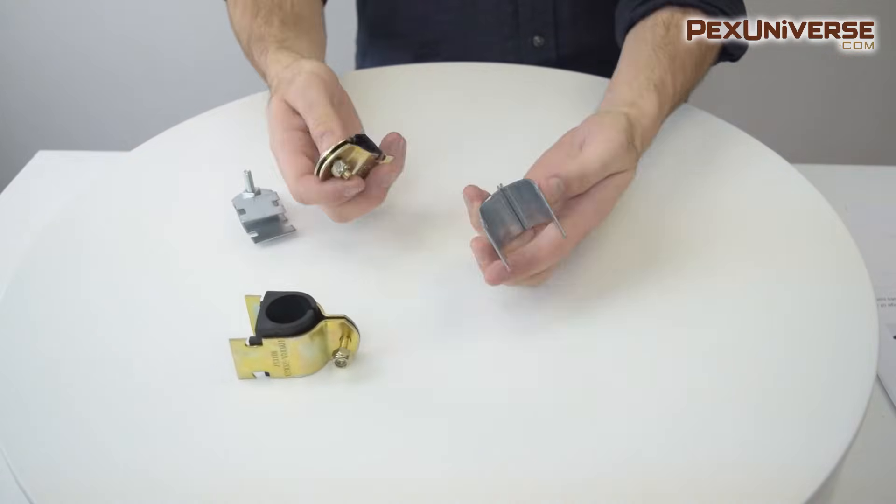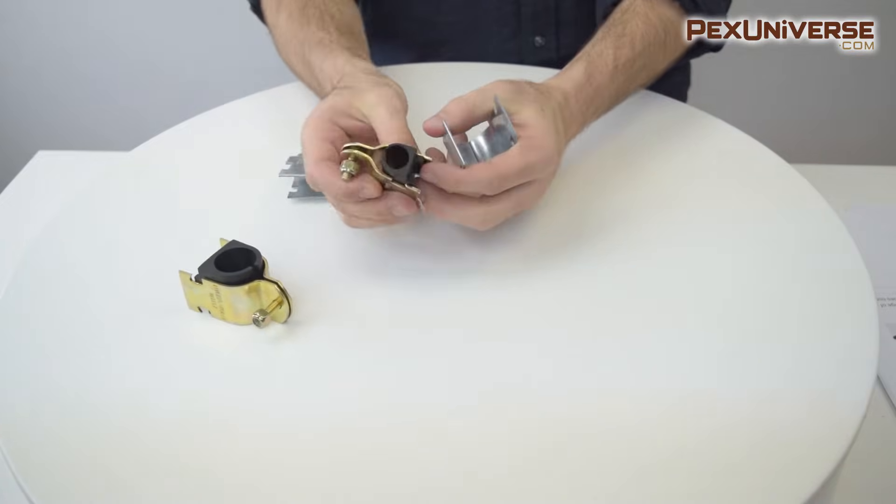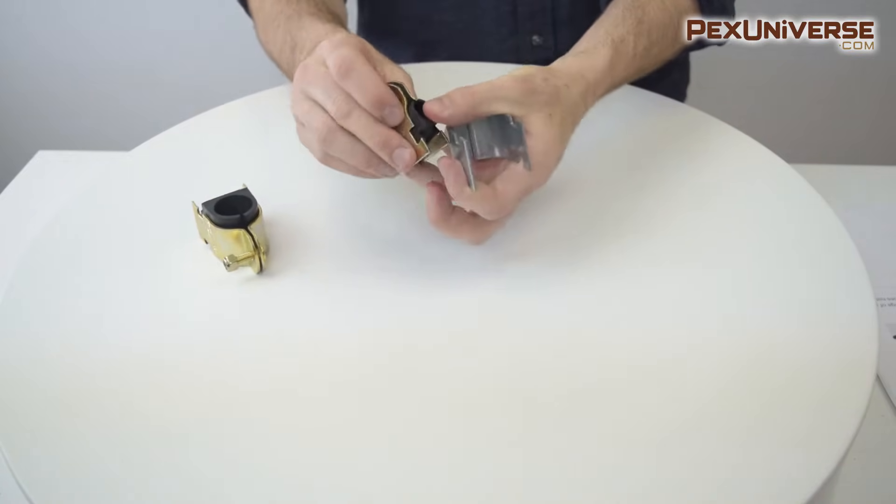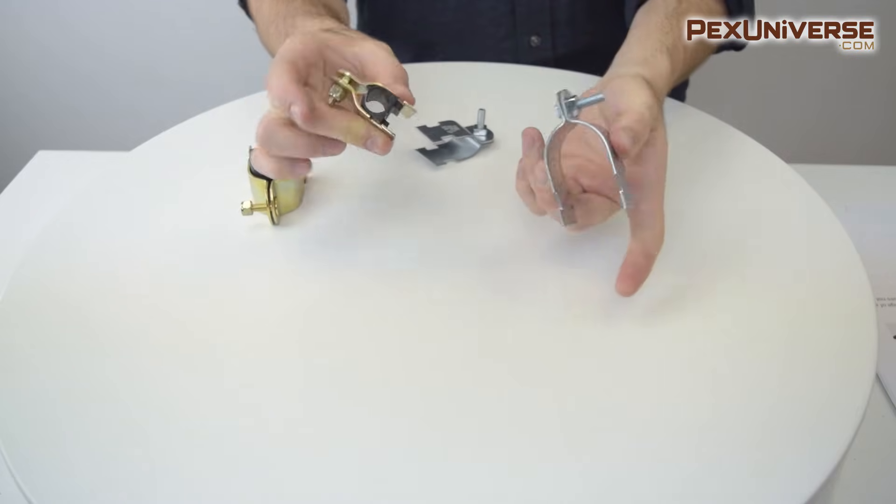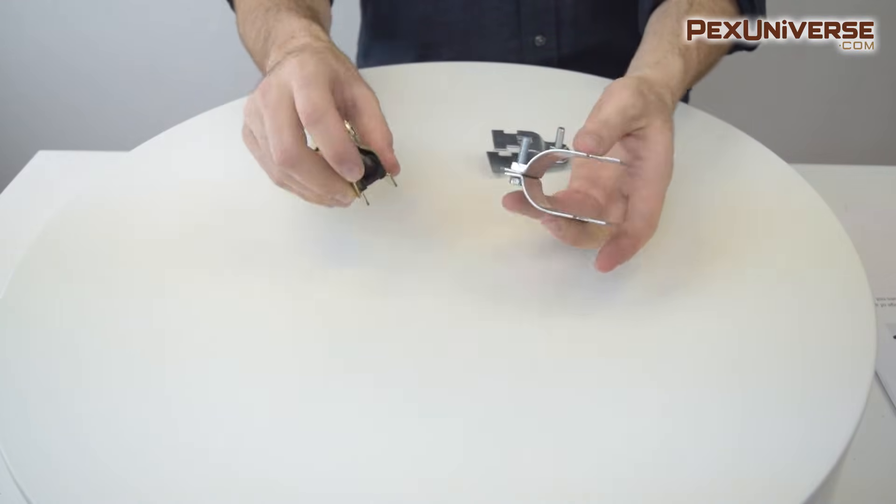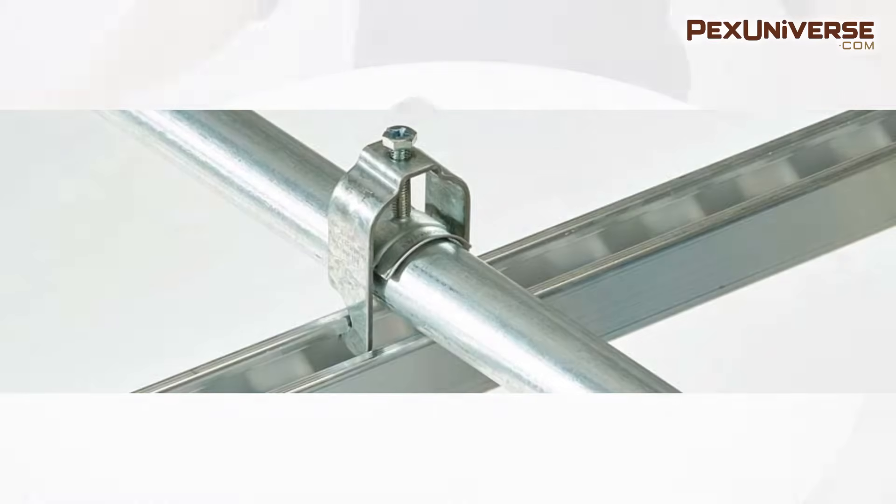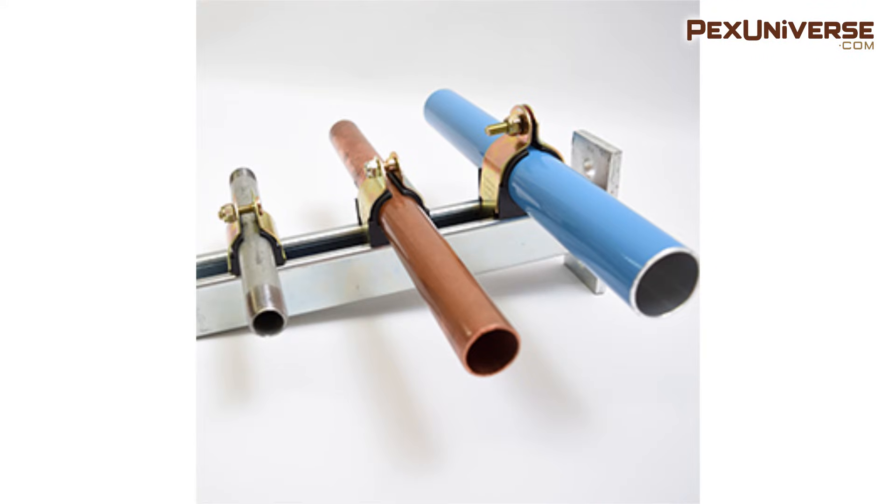Strut clamps are used to secure vertical or horizontal pipe runs to standard strut channel. Each clamp includes two brackets, one bolt and one nut. These are also called Kindorf clamps because they're used in combination with strut and Kindorf. Use cushioned clamps for copper pipe and standard clamps for all other types.